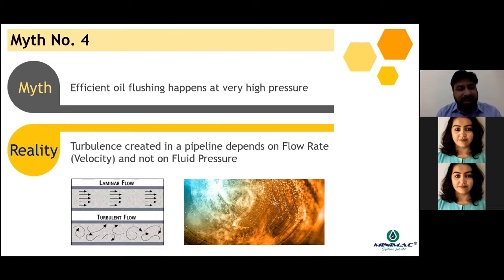At a lot of sites, we have seen that people use pressure testing equipment, which are at a very high pressure. But normally the pressure testing equipment can sustain a very low flow rate. Although the pressure sustenance is very high, the flow rate is extremely low. And with these equipment, if you perform the oil flushing, you would end up doing the high pressure testing once again, but certainly you would not be able to complete the oil flushing efficiently because the flow rate through the piping is important. There should be a movement of fluid in a turbulent fashion inside the piping. If we just create a high pressure, it would certainly test for us the hydro test for the pipelines, for the leakages, but certainly it would not solve the purpose of flushing.